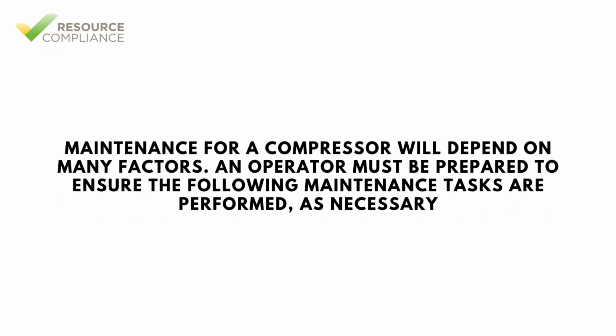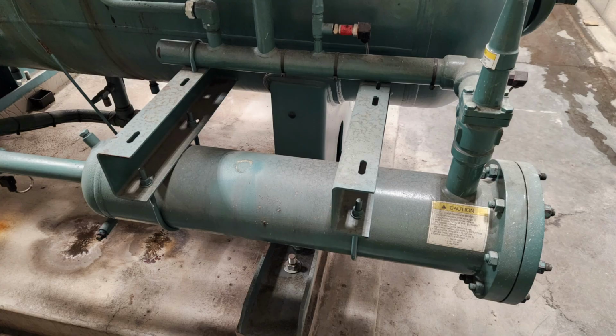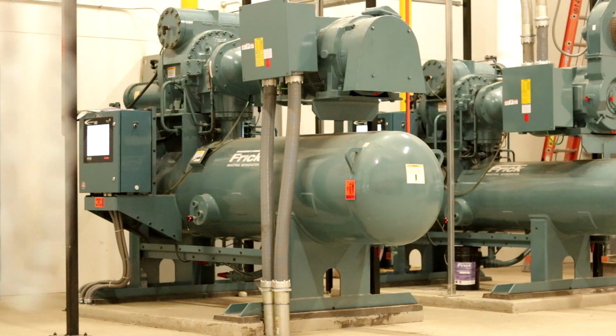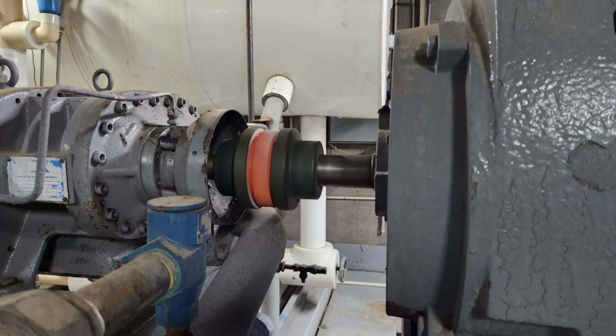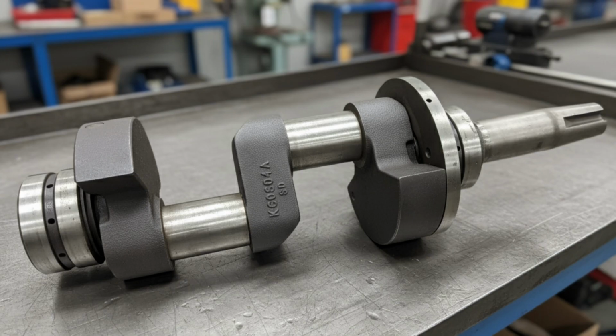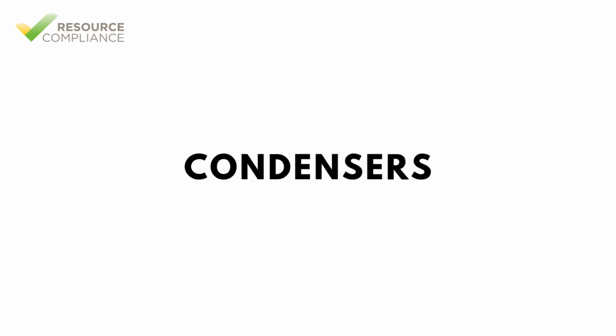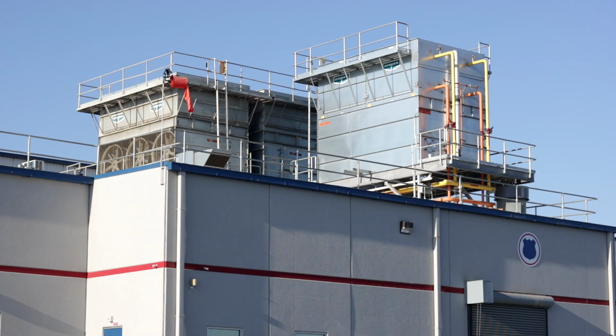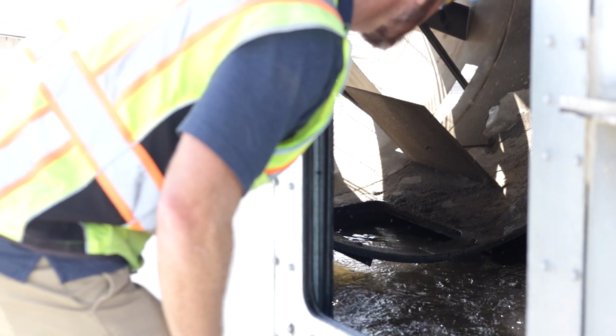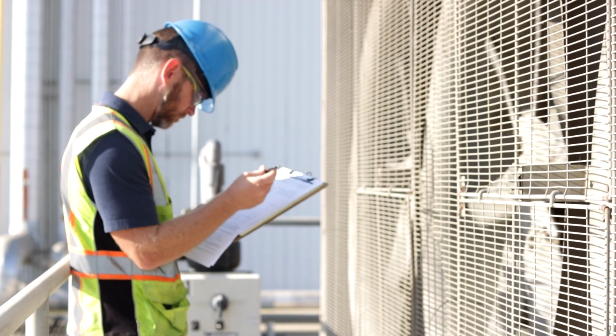Maintenance for a compressor will depend on many factors. An operator must be prepared to ensure the following maintenance tasks are performed as necessary: adding oil, changing or cleaning an oil filter, performing oil analysis, changing oil, replacing the shaft seal, and lubricating bearings. Condenser ITM tasks cover a wide range of activities. Weekly, condensers must be inspected for the following: water supply is functional and abnormal sounds and vibration.